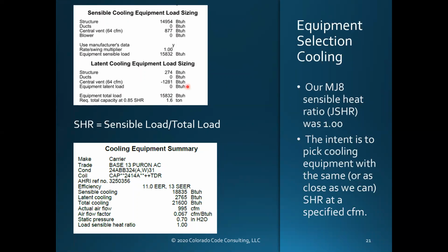Generally speaking, there isn't one, especially if you're bringing in outside air, like this example is. You're not going to see much latent load, and if you do, it's very small, generally less than 1,000 BTU. Whereas in your areas, it'll be pretty heavy.